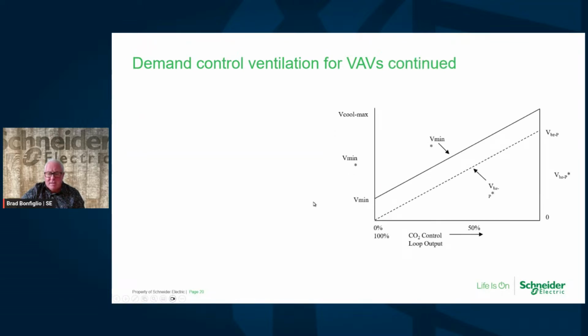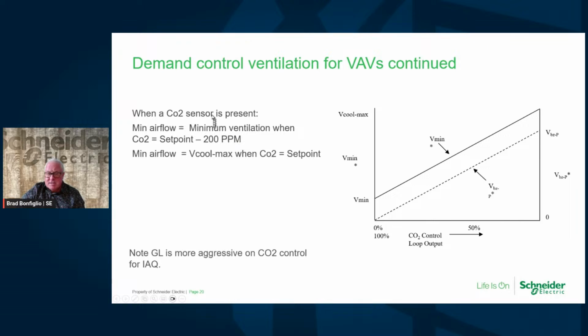The demand ventilation for VAVs, this is an interesting one. As you open up the outside air damper and you've got max and min cooling, this is part of improving indoor air quality. Normally you have a CO2 set point that's already been set up by either of the codes, for example Title 24, which sets what the parts per million is. We're actually going to take whatever that set point is, subtract 200 parts per million, and control off of that. So you're actually improving the demand ventilation above and beyond what the code allows. This is back to, we're going to typically use more energy to do this, right? Because we want to increase the indoor air quality of this application. And again, if you look back at the articles, the energy savings on average was 31%. So that includes actually doing this as part of the study.